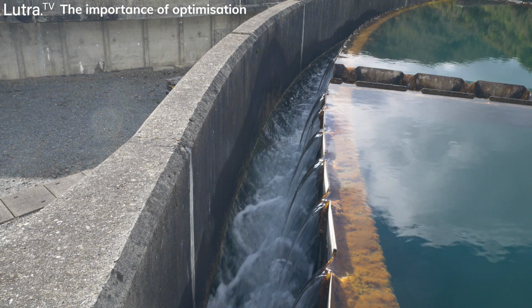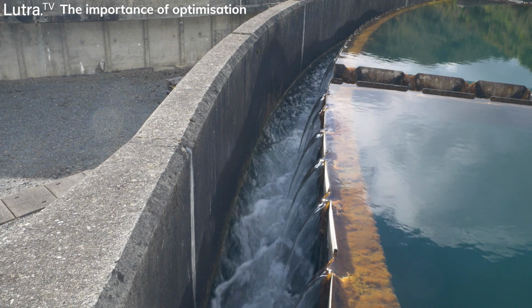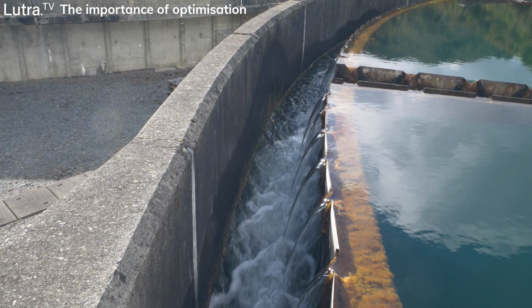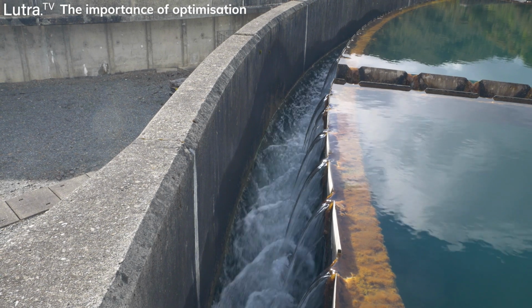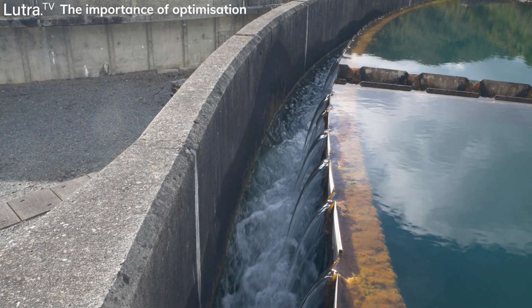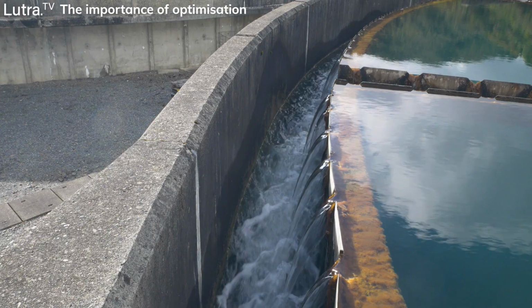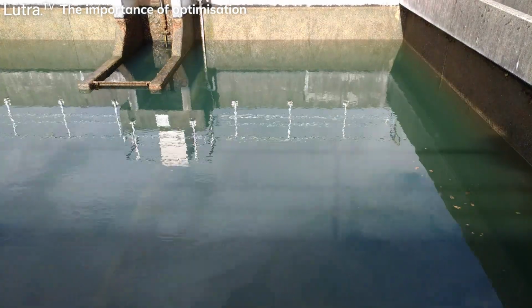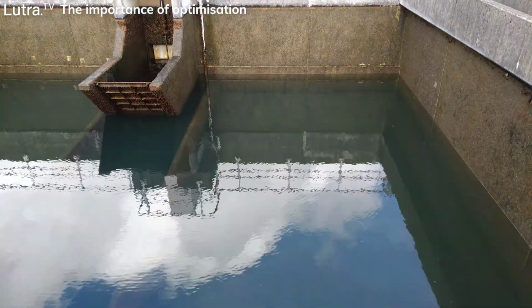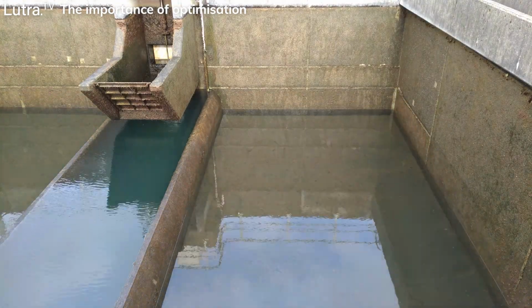Have you got any specific examples from, I guess, your experience in the field of some optimisations that have gone really well? Yeah, so a very common one would be optimising, say, clarifier turbidity. Clarifiers, by their nature, remove the primary amount of solids. But if you have slightly higher turbidity coming out of a clarifier than you might necessarily be able to achieve, that translates directly downstream to the filter performance, the backwashing, all that sort of thing.